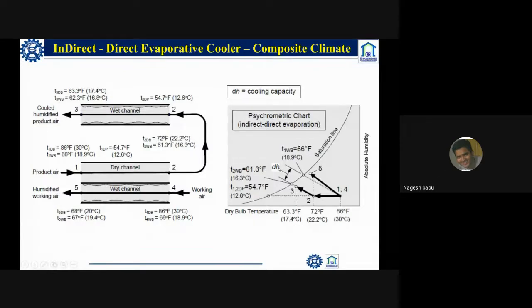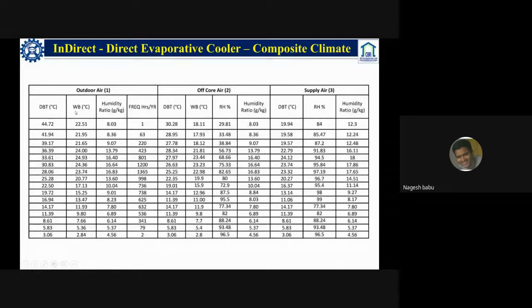So we are always thinking that we need a compressor to achieve these conditions, but these conditions can be achieved even without a compressor, without electrical energy utilization. So these are the indirect and direct evaporative cooling temperature conditions. Similarly, for the same conditions on a typical day when we have 45 degrees centigrade, the wet bulb temperature is around 22.51 degrees centigrade. But because of this combination, the dry bulb temperature can go below the wet bulb temperature, up to 19.94, that is, 20 degrees centigrade. So we can reach below the wet bulb temperatures also.